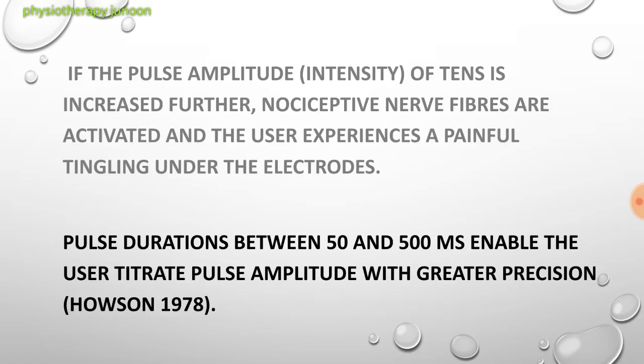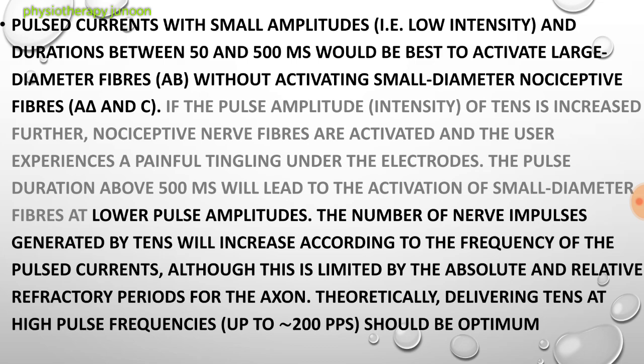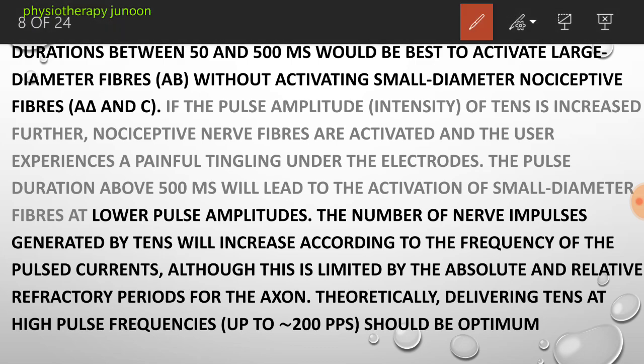If the pulse amplitude of TENS is increased further, nociceptive nerve fibers are activated and the user experiences a painful tingling under the electrodes. Pulse duration between 50 and 500 microseconds enables the user to adjust pulse amplitude with greater precision. This was studied by Howson in 1978. A pulse current with small amplitude and duration between 50 to 500 microseconds best activates large diameter fibers, specifically A-beta fibers, and not A-delta and C fibers.